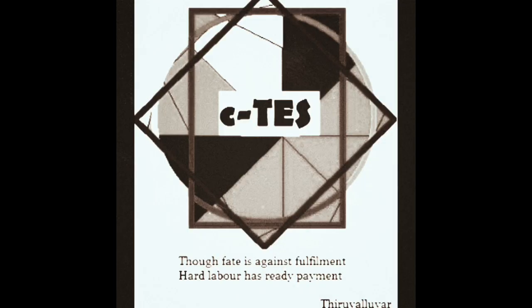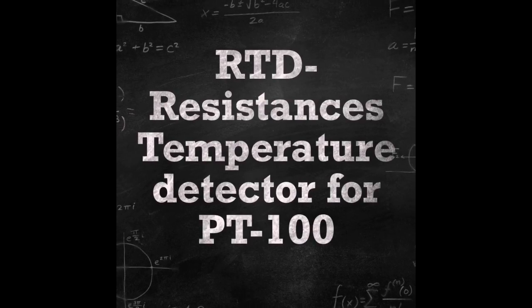One RTD sensor is PT100, which stands for Platinum 100. Now we are going to see the formula to calculate resistance for a particular temperature using PT100. The formula for PT100: RT equals R0 into 1 plus alpha T.